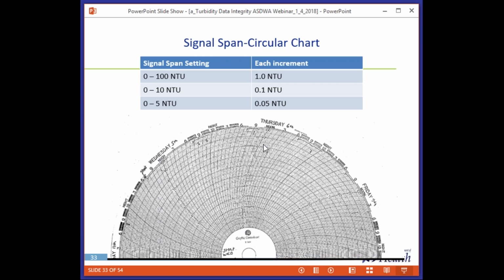turbidity standard. If you had it set from 0 to 10, then each of those tiny marks is 0.1 NTU. So for an optimized plant, the pen would just go between 2 lines for the entire time. And even if you had 0 to 5, each line would be 0.05 NTU. So this makes it hard to use a circular chart to get the resolution you need, but not to be able to detect a regulatory violation.